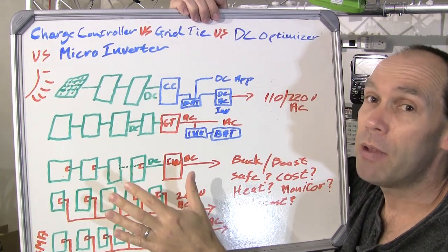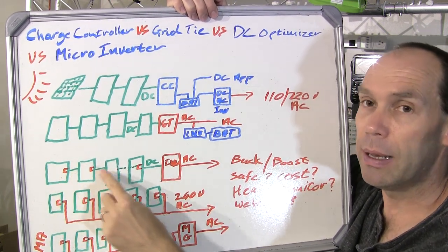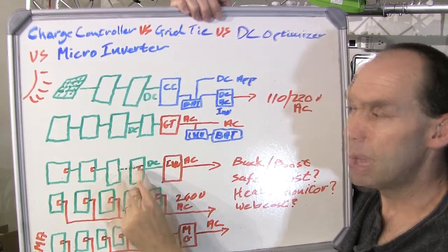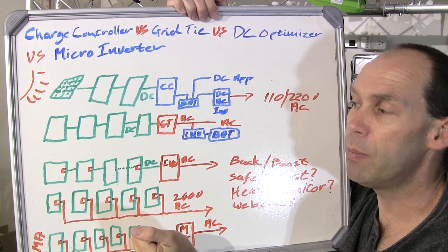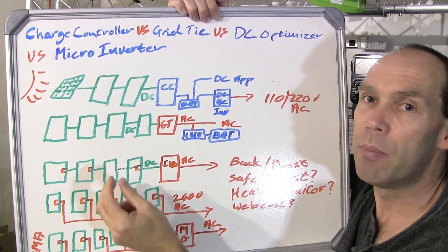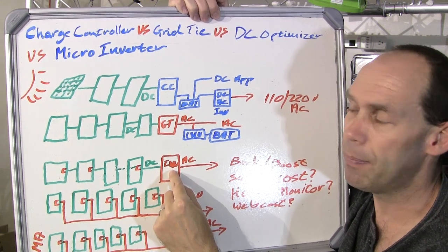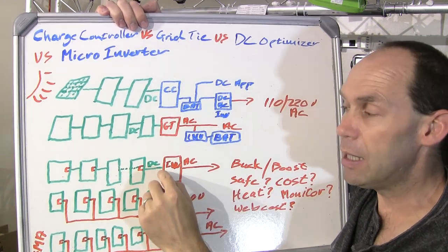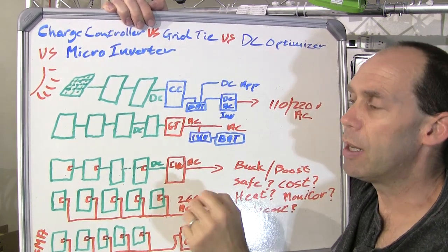However, some manufacturers do this in different ways. For the most part the panels will still be linked together in a string, and doing MPPT at each panel provides a far more flexible system so that in different light conditions each panel is performing at its optimum. It also means you can potentially put different types of panels in, because each will be optimized, and then their DC power is brought to a central inverter. The goal for these DC optimizers is basically to keep a single DC voltage level coming into an inverter, and the way different companies implement their optimization varies.